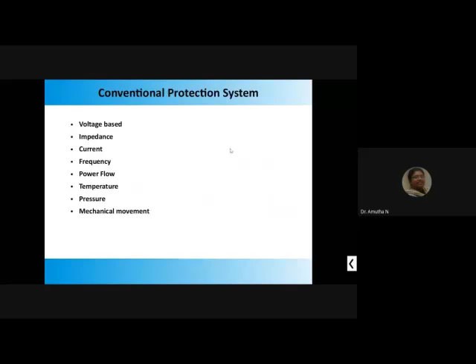With the microgrid added to the conventional grid, the original protection coordination now has to become adaptive protection coordination. In earlier cases, the protection coordination depended only on the relay characteristics. The relay senses the abnormal conditions, and based on the relay characteristics, it gives the initiation action.